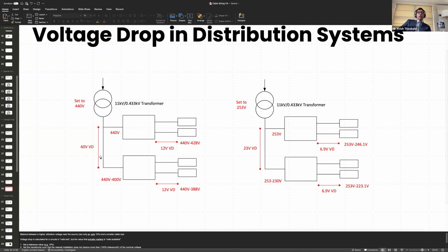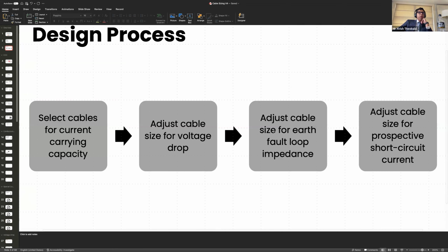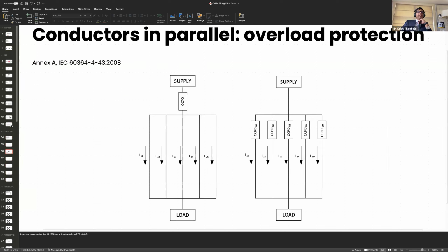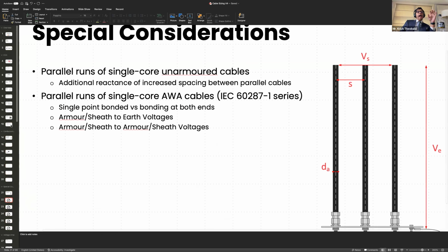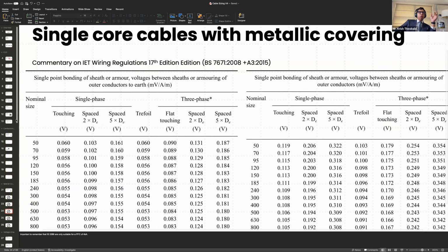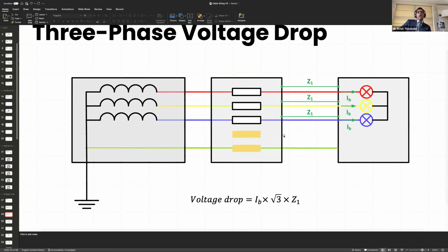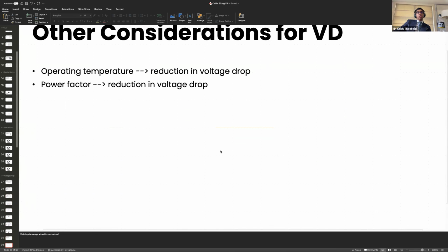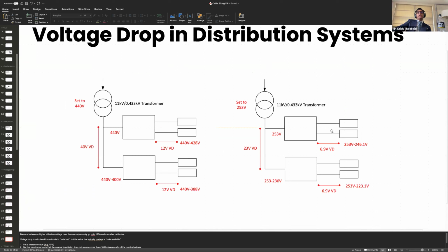But what you will notice is that if you choose a voltage drop in excess of 5%, in most cases, when you come to the third stage, the earth fault loop impedance, you are not going to satisfy earth fault loop impedance anyway, so you'll have to upsize the cable. So no, you do not have to restrict it to 5% in an industry. These values are guidance for when there is an absence of information on the connected load, but in an industry that will not be the case. And like I said earlier, in a larger network the consideration is utilization voltage, not this 3%, 5%, and so on. Okay, now there are a few questions regarding harmonics.